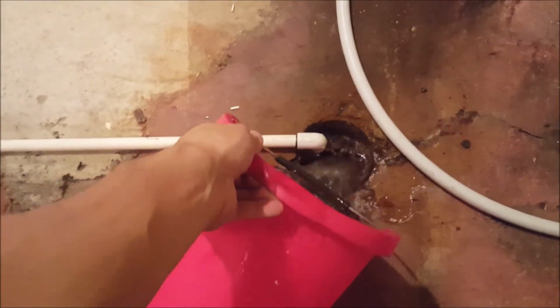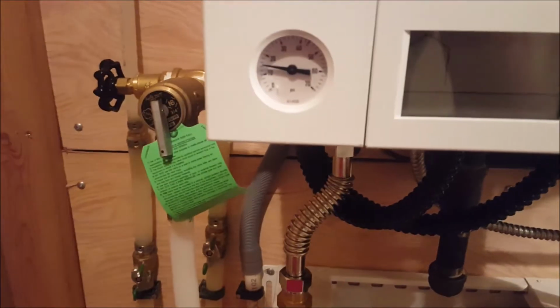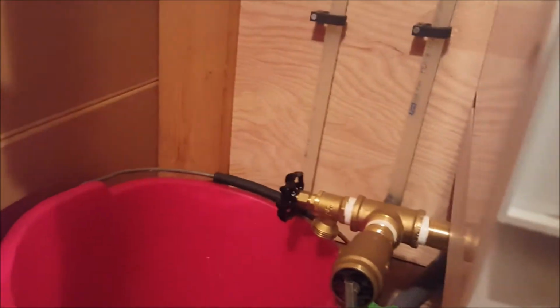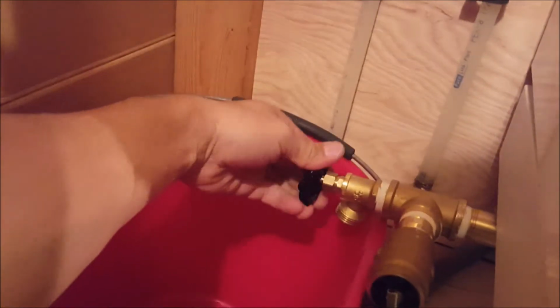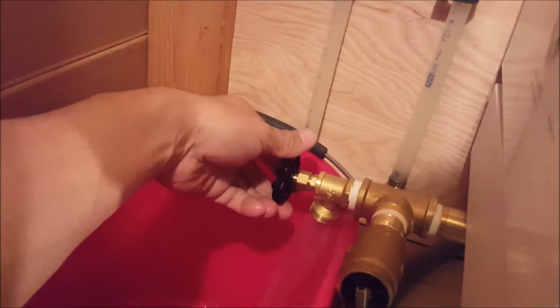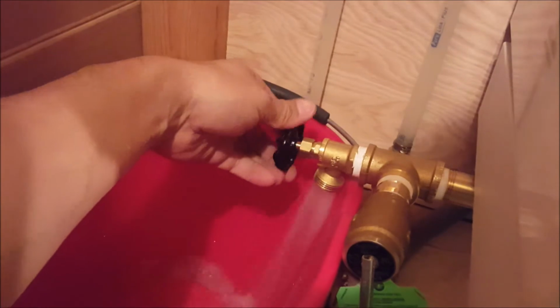To make sure there's no air in there, but there shouldn't be too much going on. I'll just dump that down the floor drain here. Our pressure looks reasonable, about 15 psi, which should be about right when it's cold. I'm going to turn this one on now and run it for a few moments to get any air out.